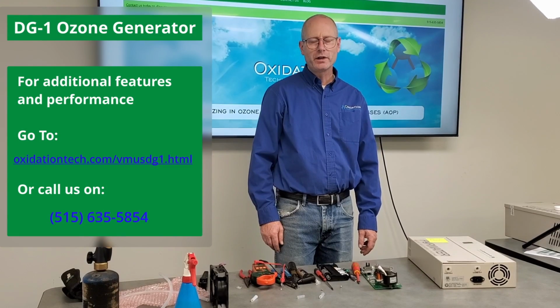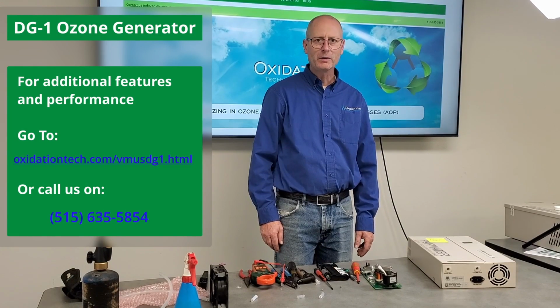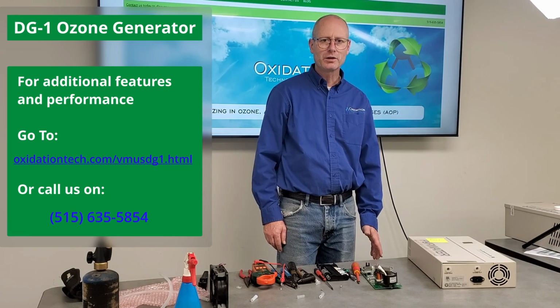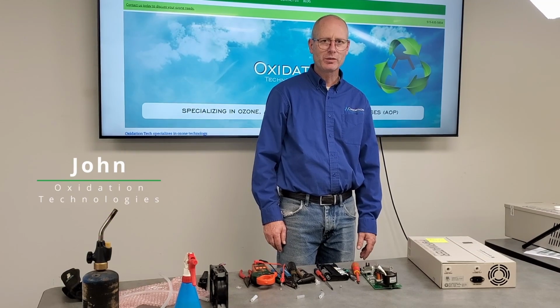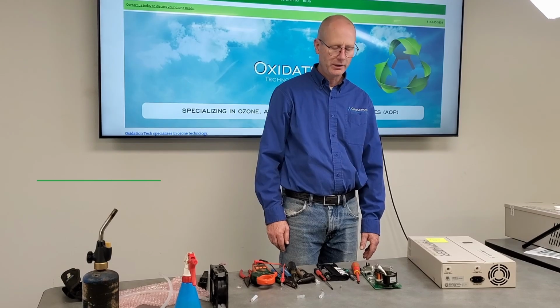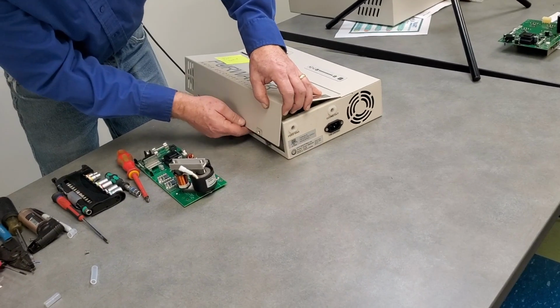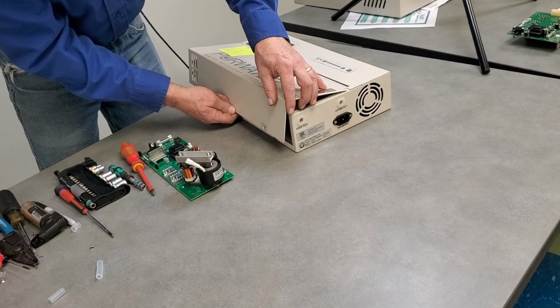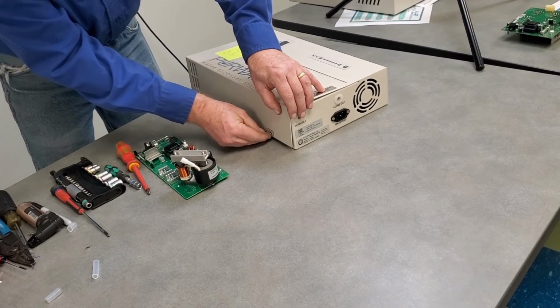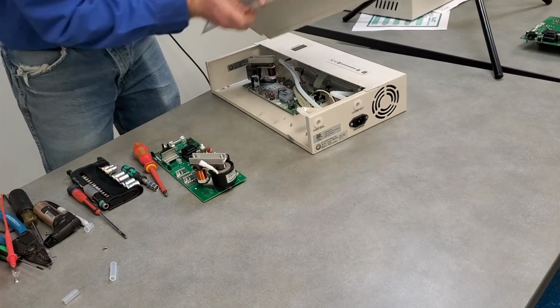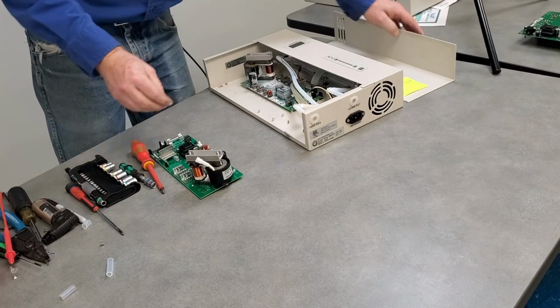We've got a DG-1 ozone generator here that's not working, and wanted to go through it with you and show you some of the things that typically will need repair on these. There may be a seal here that you'll want to just remove. Take these two screws out and this cover comes loose.